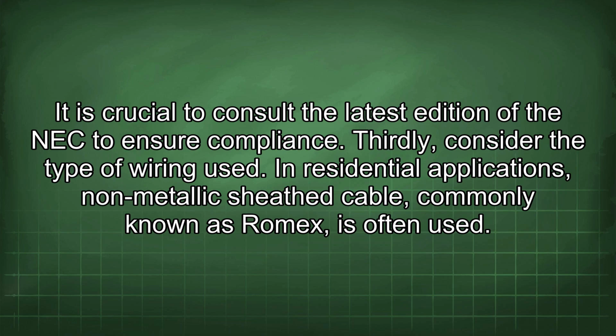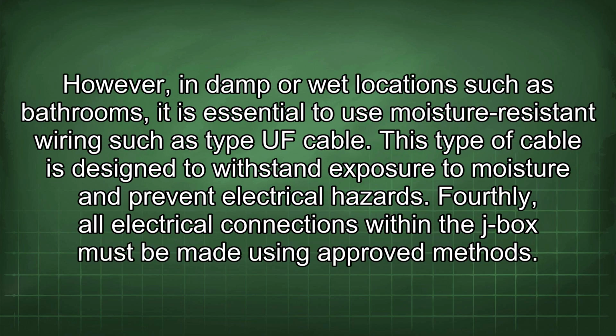Thirdly, consider the type of wiring used. In residential applications, non-metallic sheath cable, commonly known as Romex, is often used. However, in damp or wet locations such as bathrooms, it is essential to use moisture-resistant wiring such as Type UF cable. This type of cable is designed to withstand exposure to moisture and prevent electrical hazards.